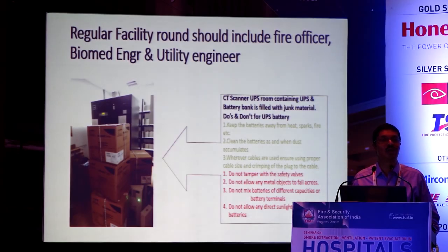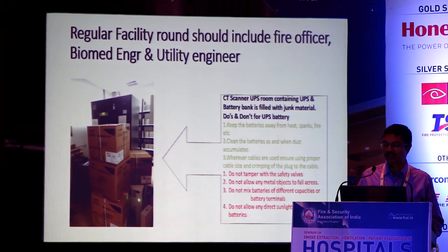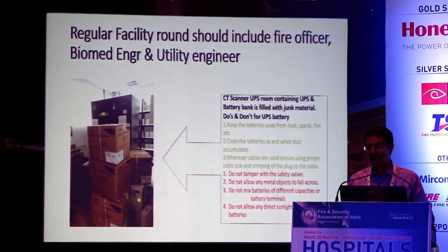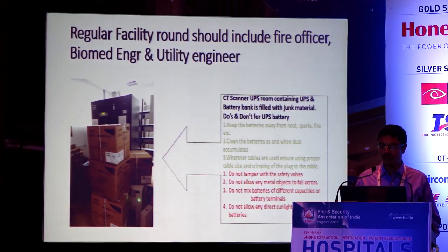Some do's and don'ts for the UPS batteries. Keep the batteries away from heat, sparks and fire, clean the batteries, and ensure that the cables are of proper size and clamped properly. Do not tamper with the safety valves. Do not allow any metallic objects to fall across. Do not allow direct sunlight. In a hospital there is the central UPS as well as the UPS used along with the medical equipment. Please ensure that these are taken care of properly.